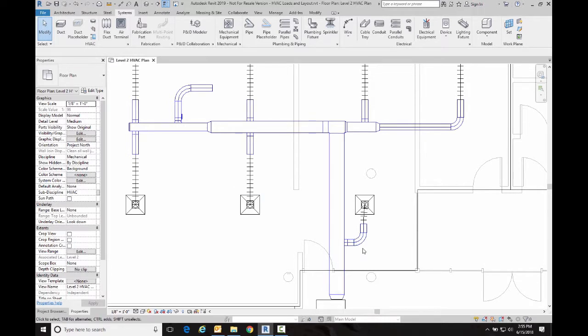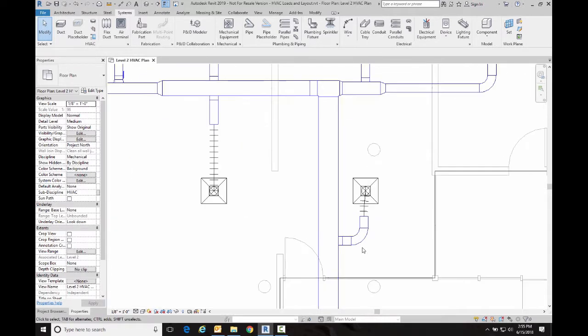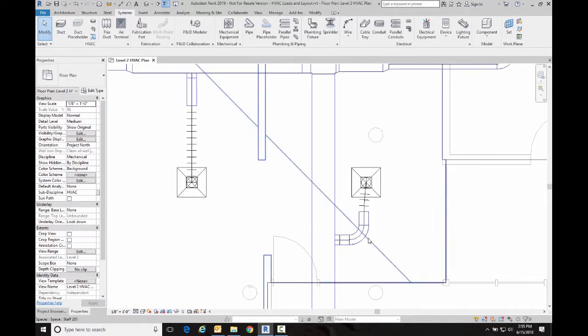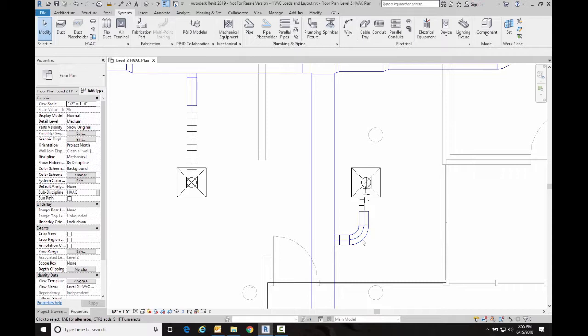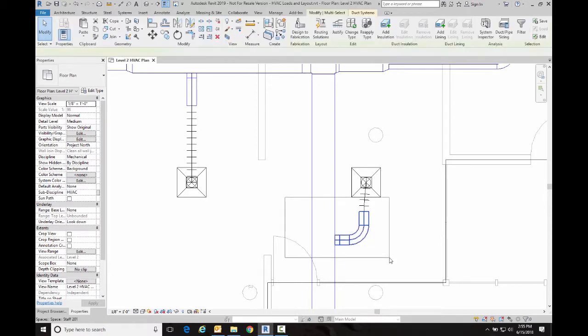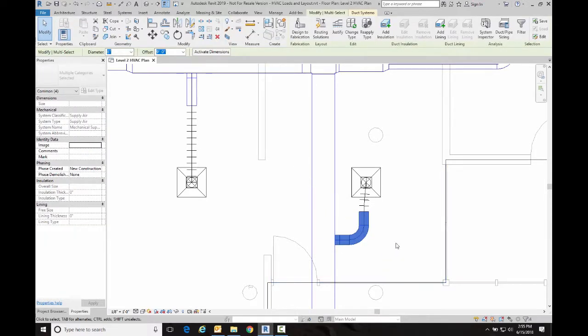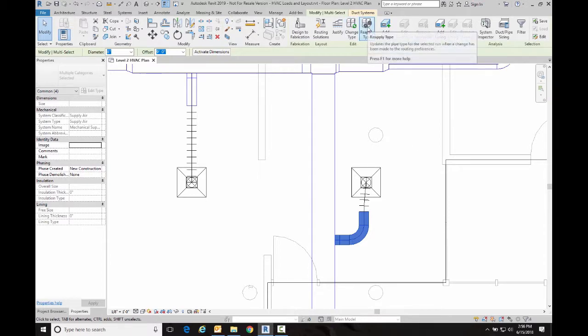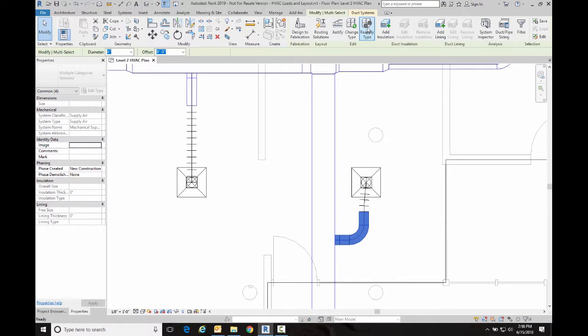Now down here I have an existing duct and it has an elbow in it, so we will see this elbow get longer. So I want to update this existing duct. Now this is a multi-segment duct. I've had really good luck with reapplying type with a multi-segment duct, so we're going to go up here to reapply type.